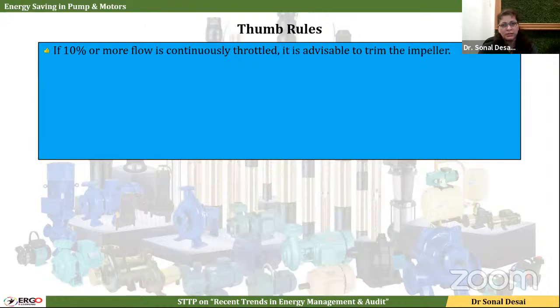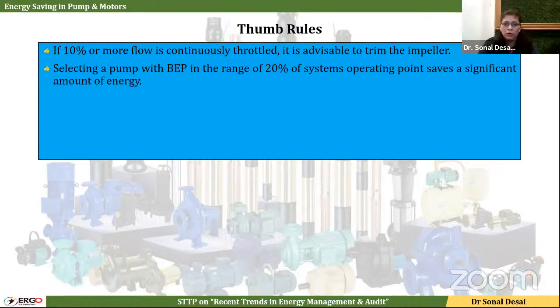And to summarize the first part of my presentation, that is pumping energy saving. If 10% or more flow is continuously throttled, trim the impeller. Your pump should always operate in and around 20% of the best efficiency point. Remember, we cannot make it always operate at the same point. Again, voltage induced variation will always be there. So 10% here and there is always okay.